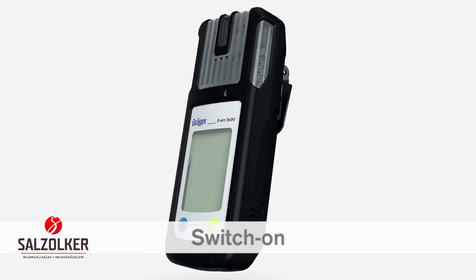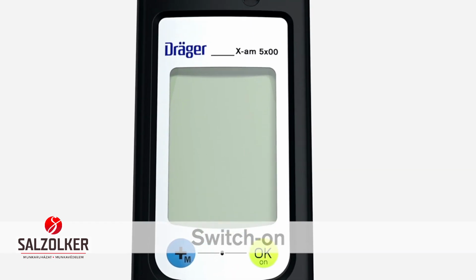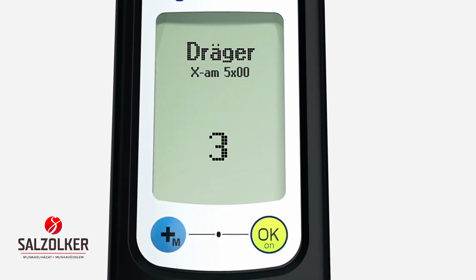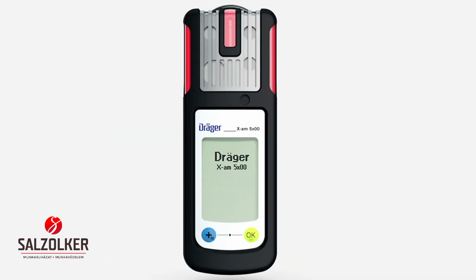To turn on the device, press and hold down the OK button for 3 seconds. A countdown is now shown on the display. The LEDs flash and the vibration alarm pulses once the device has been successfully turned on. The instrument starts the boot sequence and performs an automatic self-test. The self-test screen shows the installed software version, the special symbols, the number of days until the next calibration, the alarm threshold for each gas, the TWA and STEL alarm thresholds.